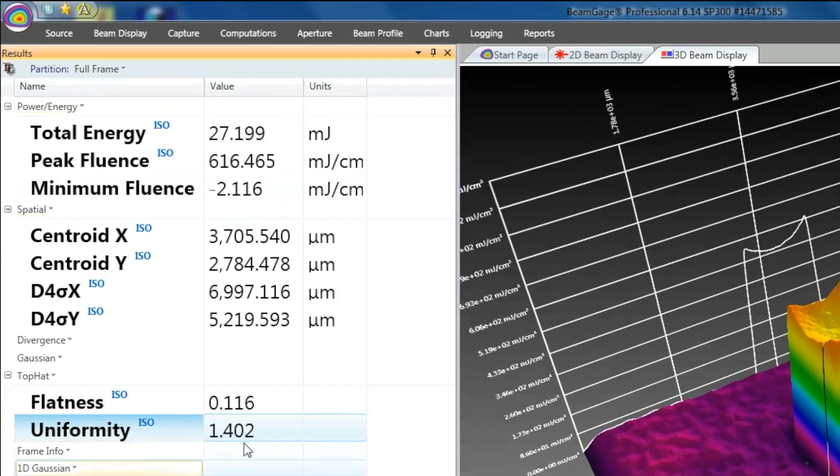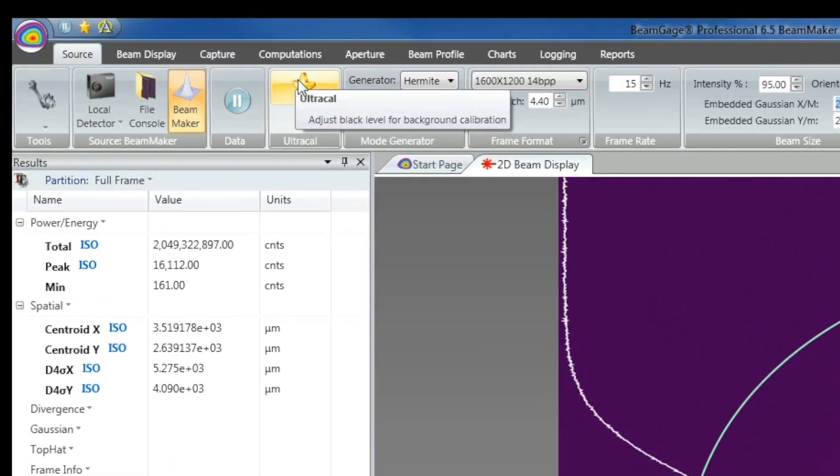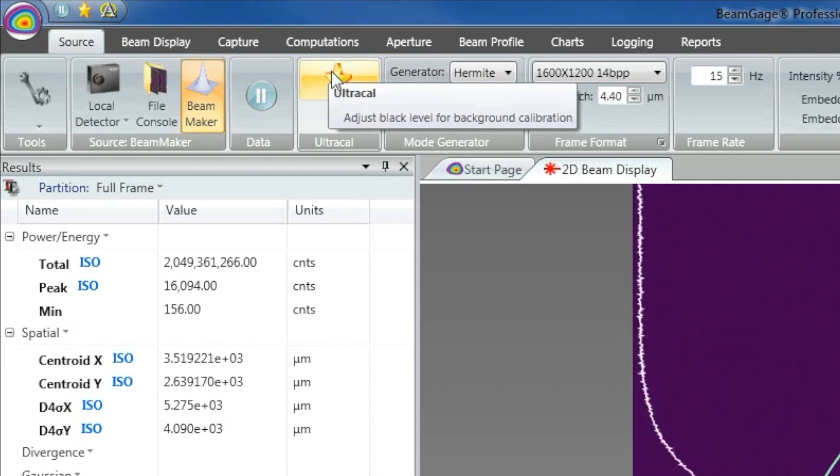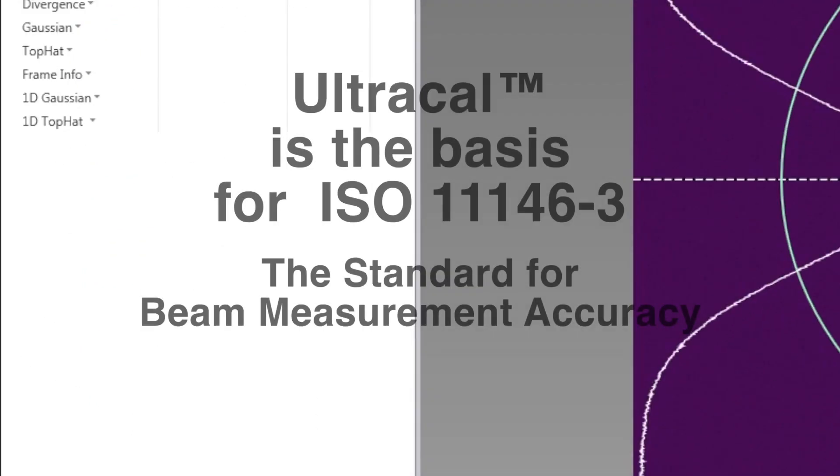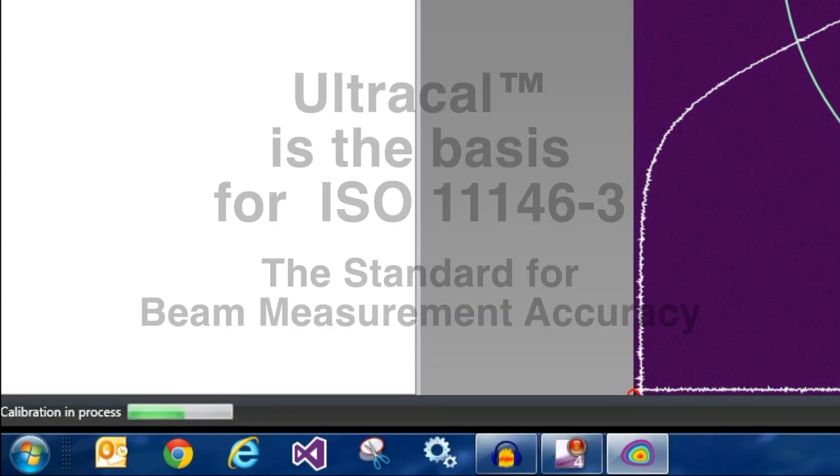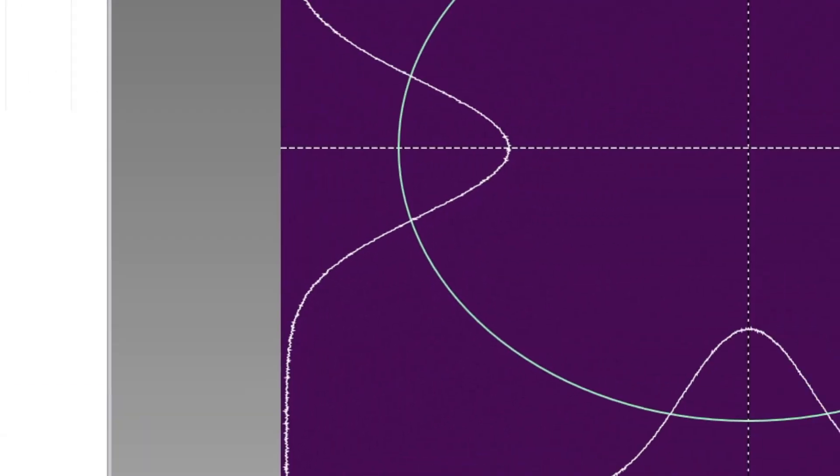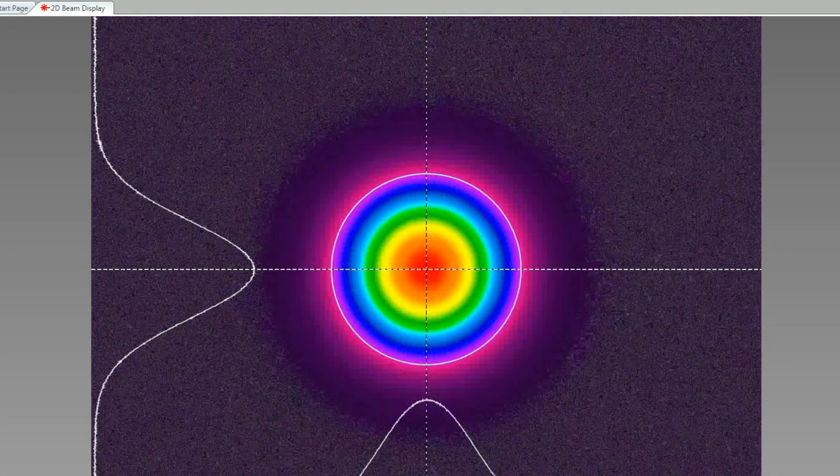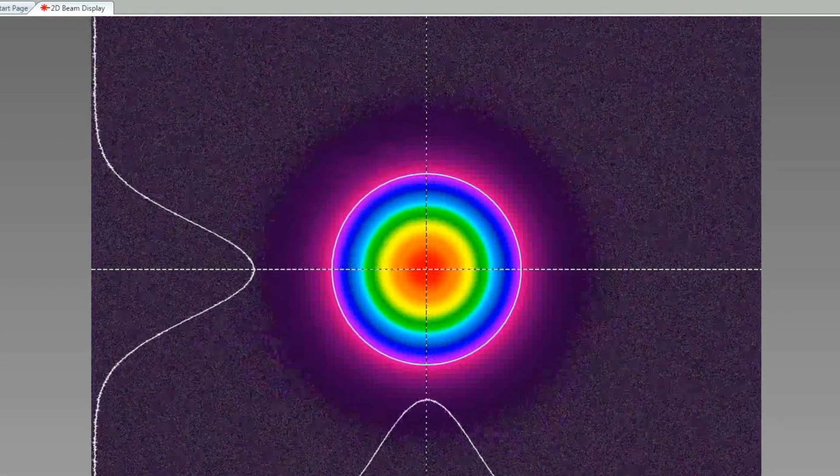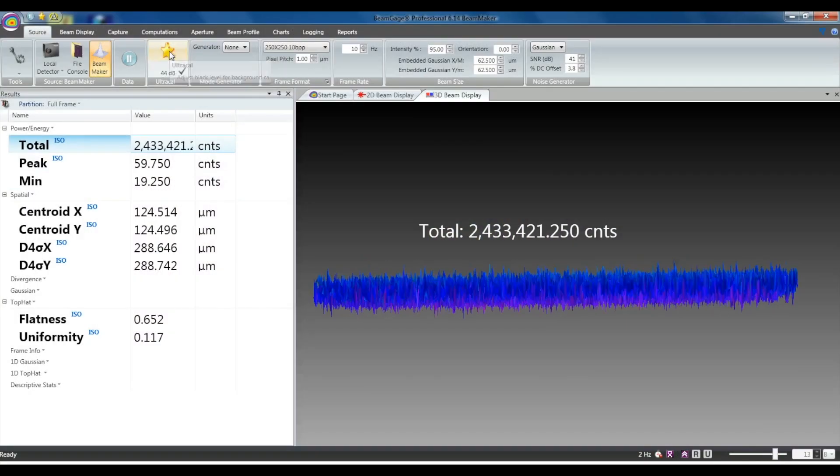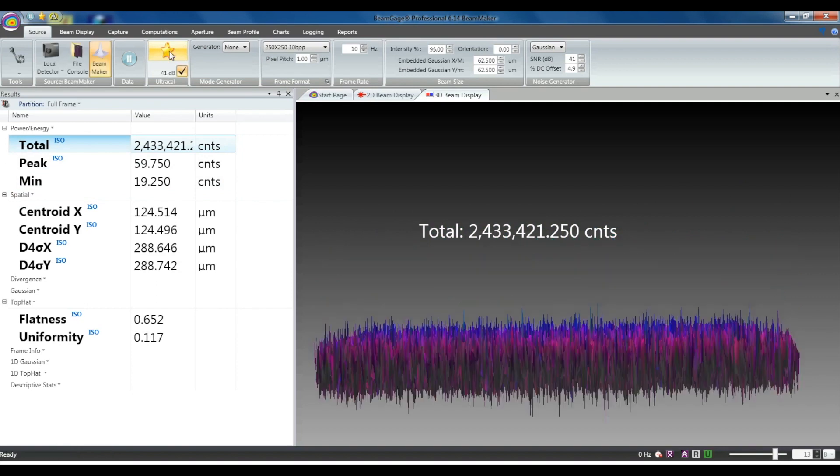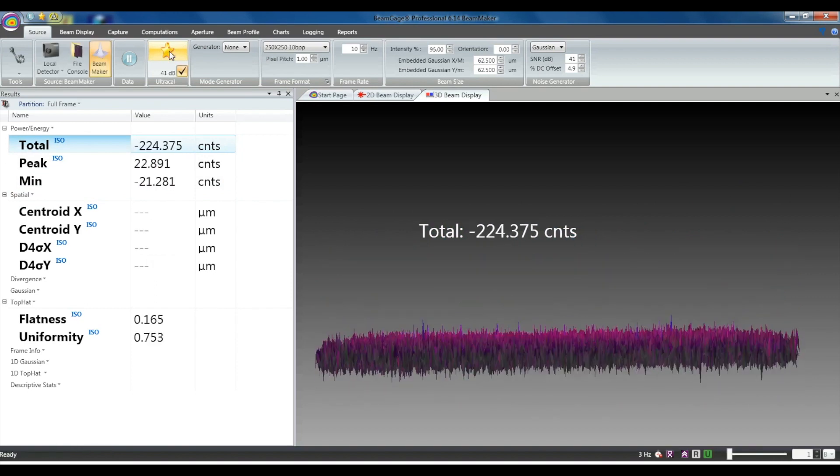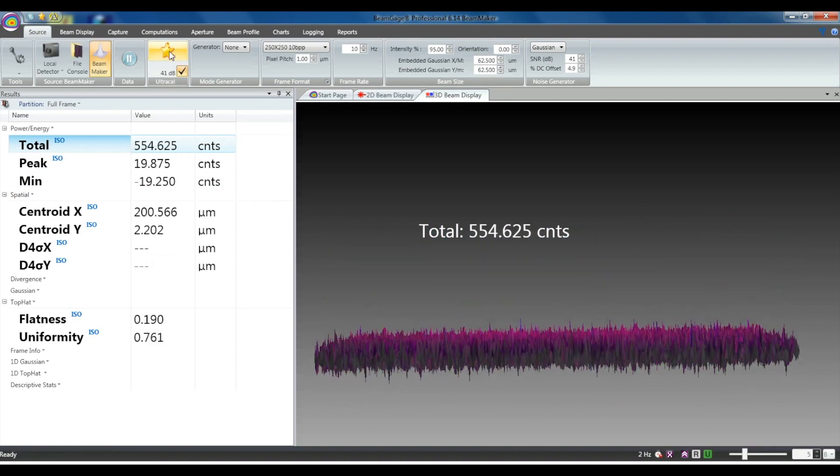BeamGage includes an extensive set of ISO quantitative measurements and features its patented Ultracal algorithm, providing the industry's highest accuracy measurements. Ultracal helped establish the ISO 11146-3 standard for beam measurement accuracy. The baseline, or zero of a camera, will drift with time and temperature changes and include random noise. Ultracal is the only beam profiler algorithm that sets the baseline to zero and in the center of the noise.